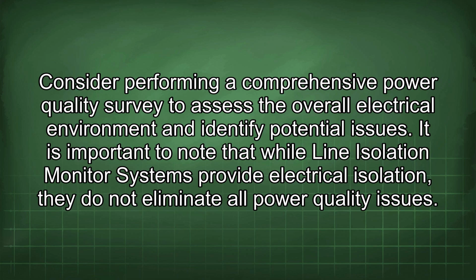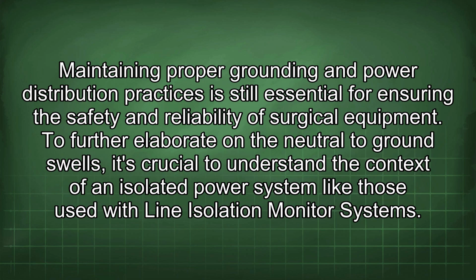It is important to note that while line isolation monitor systems provide electrical isolation, they do not eliminate all power quality issues. Maintaining proper grounding and power distribution practices is still essential for ensuring the safety and reliability of surgical equipment. To further elaborate on the neutral to ground swells, it's crucial to understand the context of an isolated power system like those used with line isolation monitor systems.